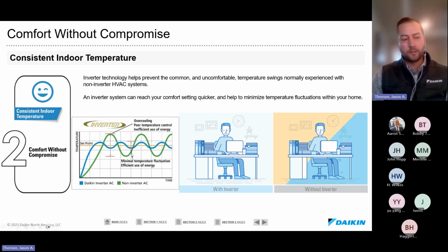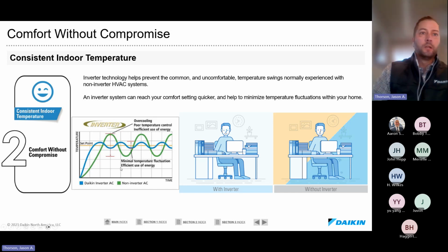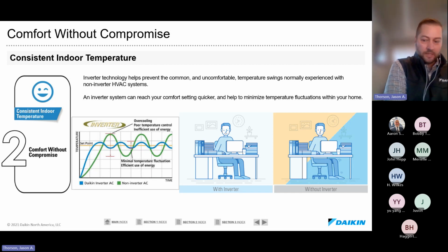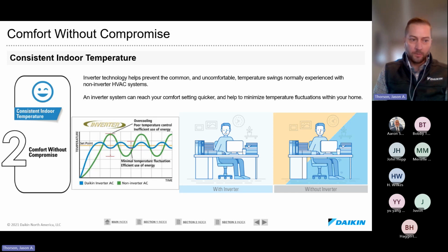We've all heard of a single speed AC unit or a 2-speed variable speed. Inverter truly is the maximum of variable speed, with 600 plus positions of adjustment up and down for cooling or heating, just what's needed to dial in that set point. We use the car analogy a lot. If you look at this graph, a single speed AC unit is like a car with only 2 speeds, 0 and 55, which is incredibly inefficient for driving around town.